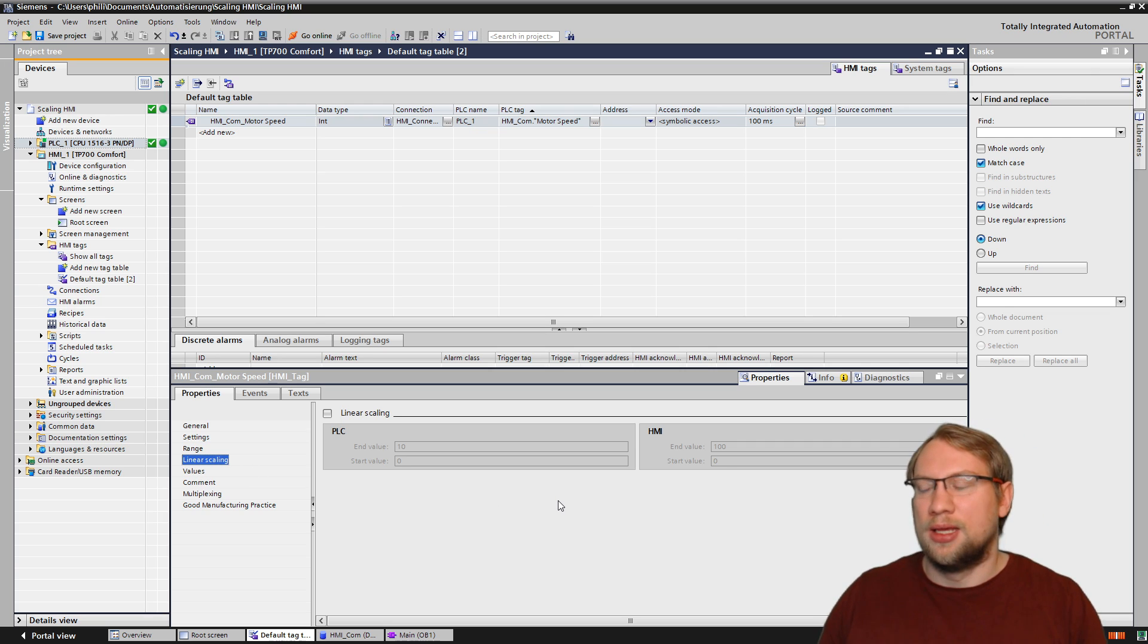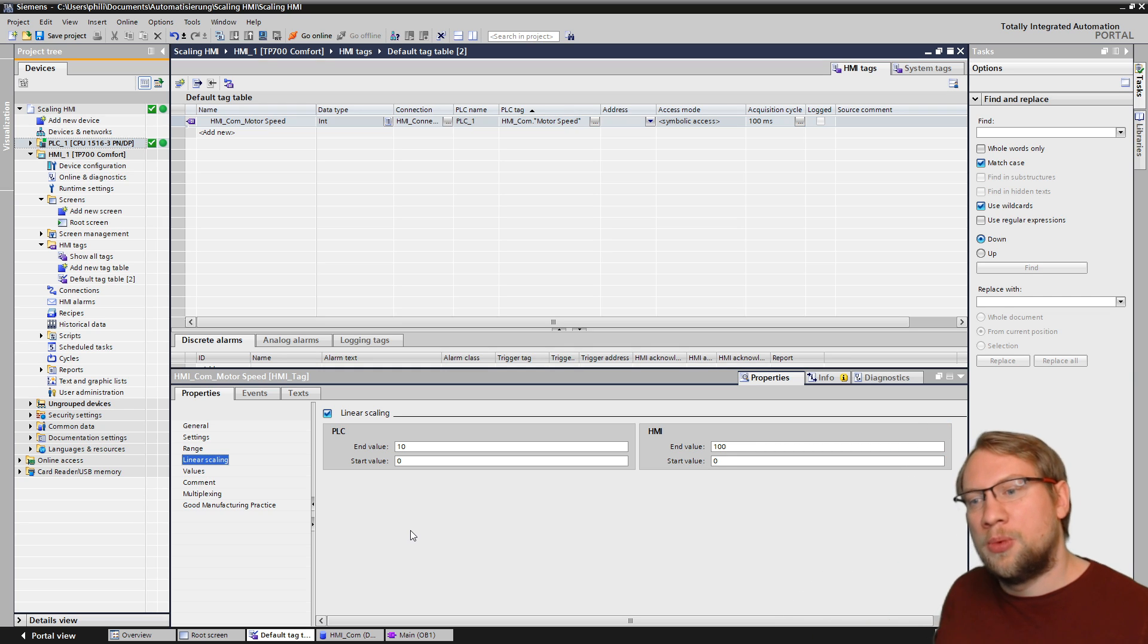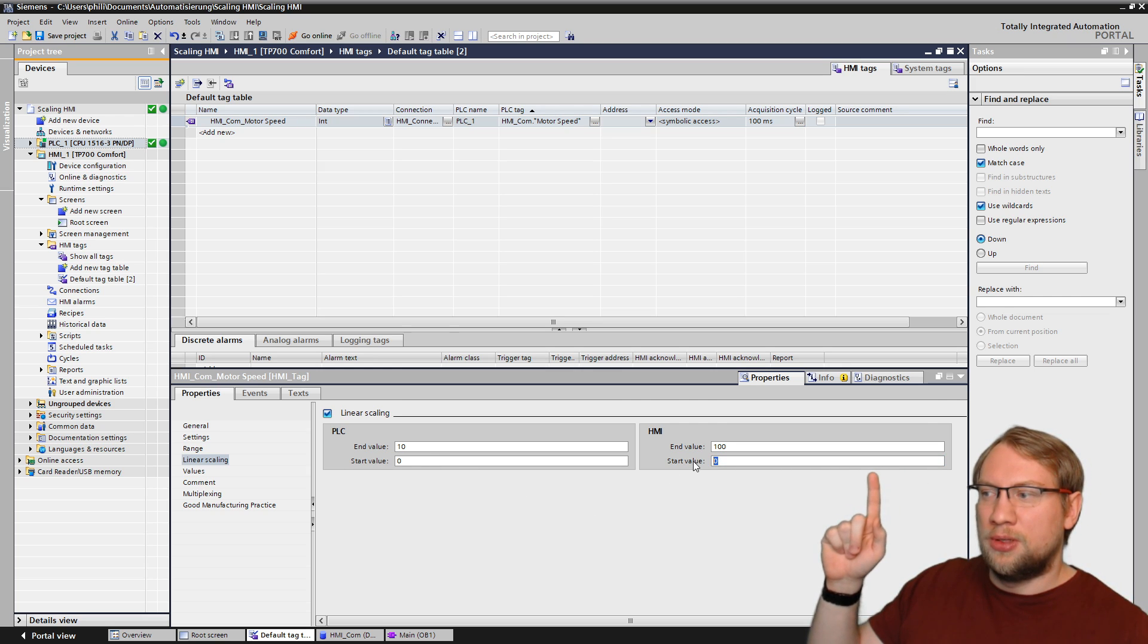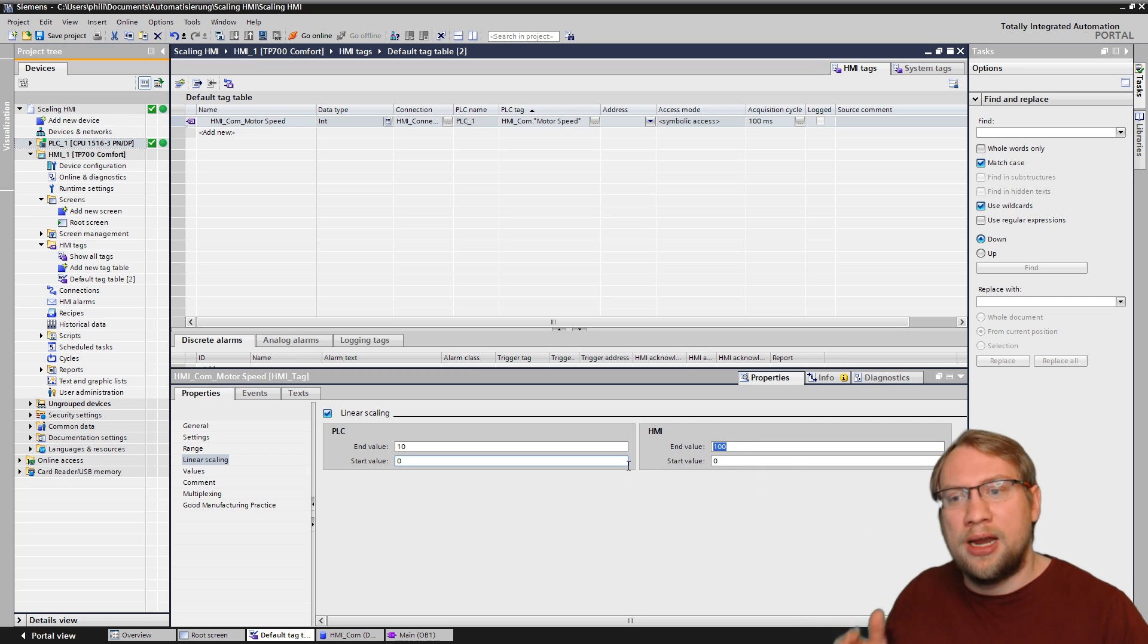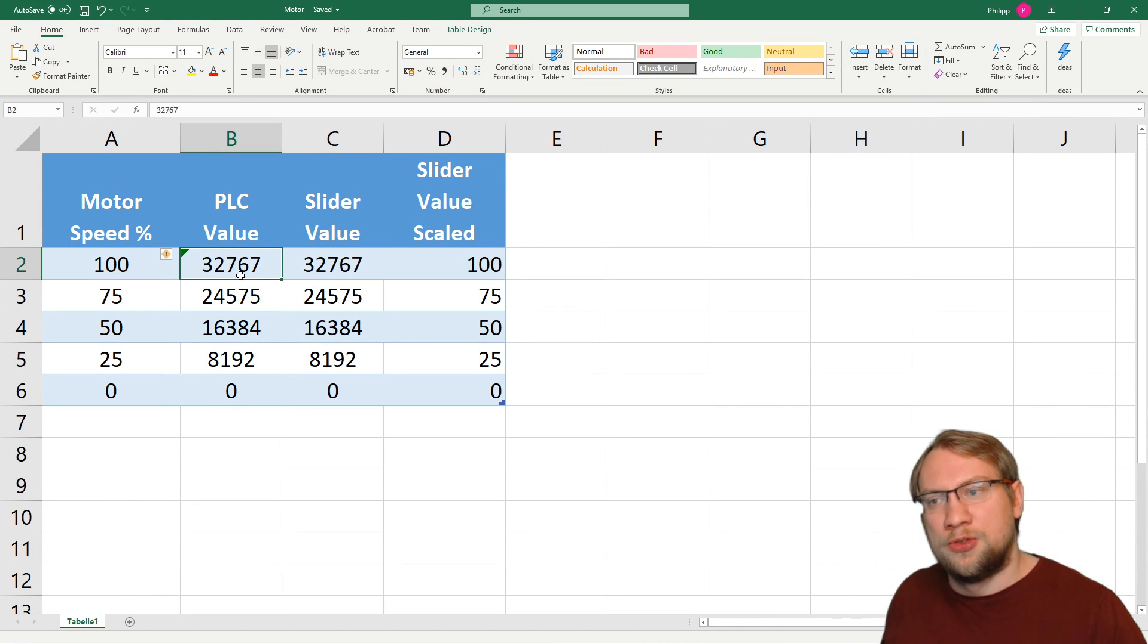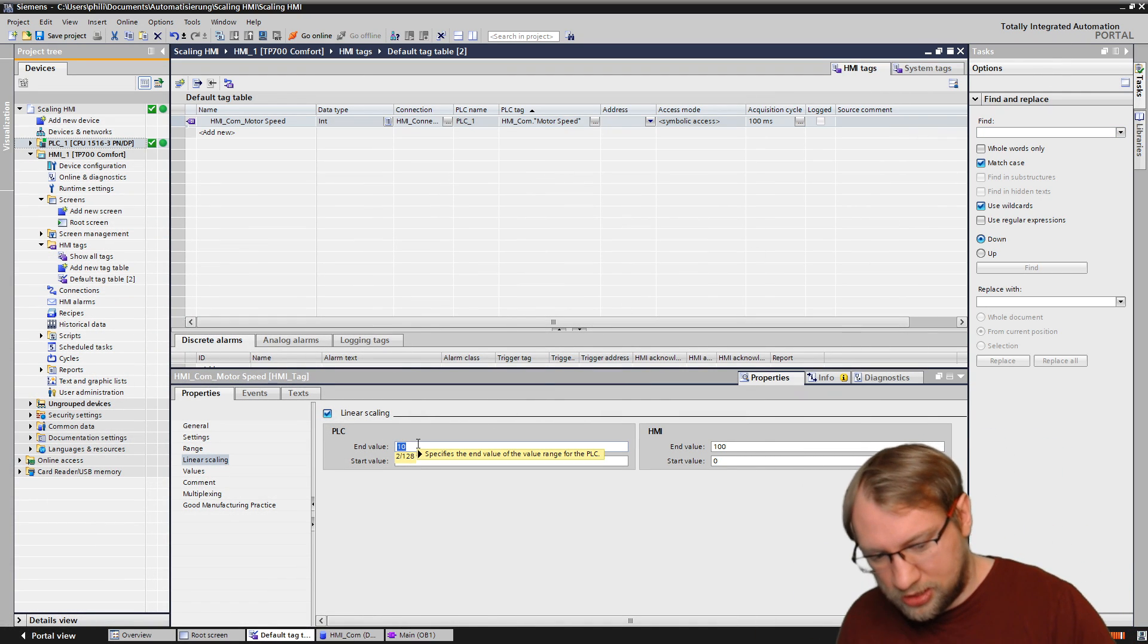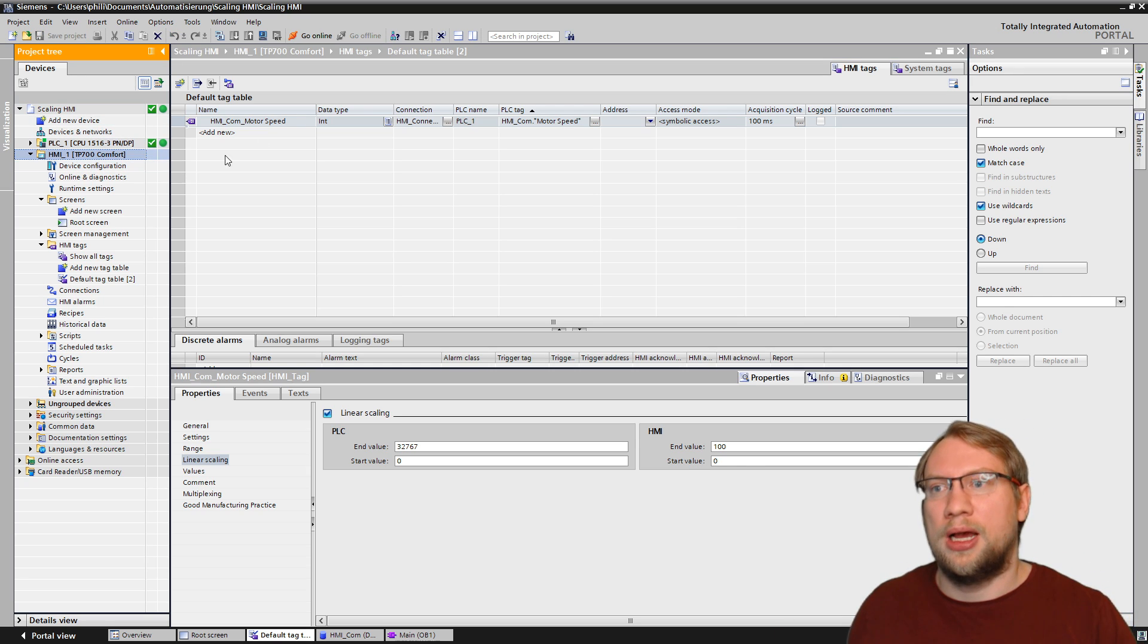In here, we have more infos about the variable we have actually selected up here. In properties, properties. There is the range, for example. I could choose upper and lower ranges by just saying here, hey, upper limit should be some value. I should not be able to go above 100 or so. Not going to do that right now. I'm not talking about limits. We talk about linear scaling. There's linear scaling. I can activate the linear scaling for every single variable on its own. And now, what do I want to have? On the HMI and PLC, it should be a bit different. On the HMI, if I have a zero, that should be in the PLC also a zero. Other side, if I have on the HMI a 100, that should be, if I have a 100 on the HMI, that should be the 32,767 on my PLC because that is the same as 100%. For the PLC, we need to do that because the PLC thinks that's 100%. So, I'll type that in here. All right. I type that number in and that's it. That's it. I save now.